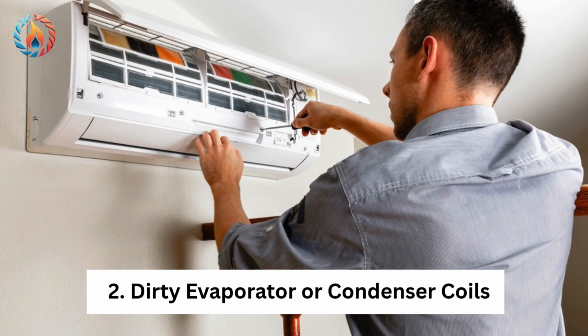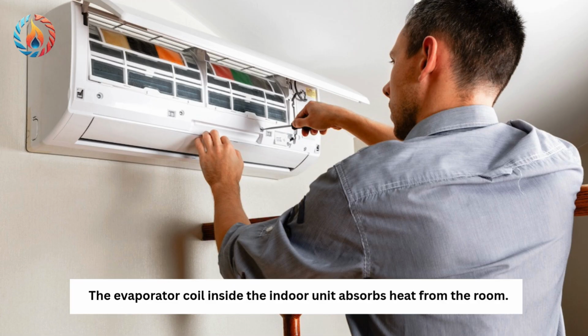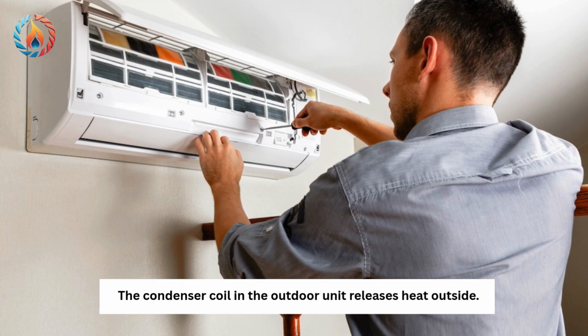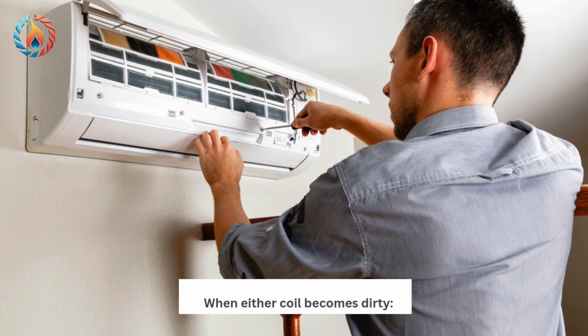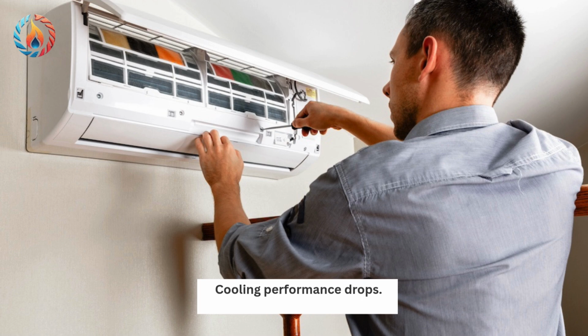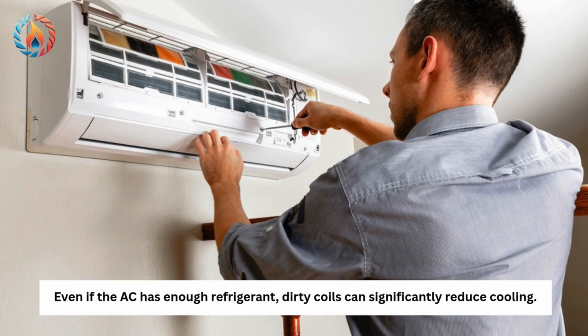2. Dirty evaporator or condenser coils. The evaporator coil inside the indoor unit absorbs heat from the room. The condenser coil in the outdoor unit releases heat outside. When either coil becomes dirty, heat transfer efficiency decreases. Cooling performance drops. Compressor workload increases. Electricity bills rise. Even if the AC has enough refrigerant, dirty coils can significantly reduce cooling.